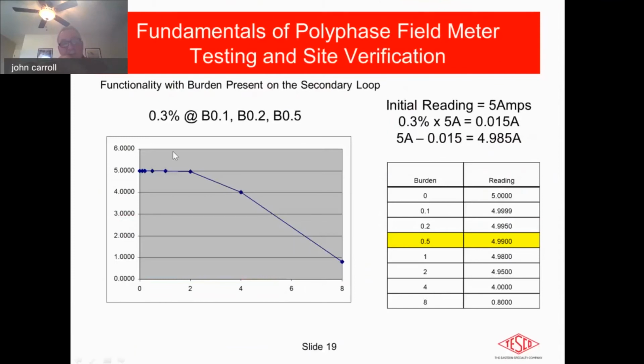Okay, so we talked before about the 0.3% accuracy rating. There it is. This is a quick little diagram, or graphic, for you, and on the right-hand side, a quick explanation of some of the math that's taking place here. We mentioned 0.3% of those burden ratings. So 0.3%, say at 5 amps, would give us 0.015 amps of error, or variation. If you deduct that from the 5, you're looking at 4.985, which would still meet that specification. If we look down at the burdens on the graph, which we printed out, you can see at 0.5, it's 4.9900. So it's just above that level.